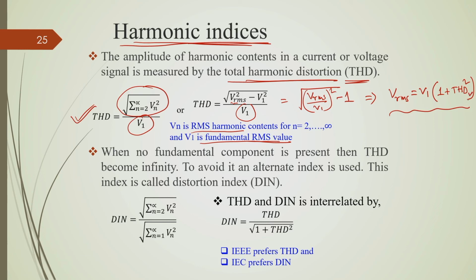So, this is the voltage harmonics which is represented by THD V. Similarly, for current harmonics we can write I RMS is equal to I 1, where I 1 is the fundamental component of the current, multiplied by square root of 1 plus THD I square. So, here this THD I represents the harmonics in the load current or line current. Okay. So, there is another index which is called distortion index. This is for the same purpose, to quantify this distortion. So, that is called distortion index. Here numerator is same as that of THD, and the denominator is different. Instead of this fundamental voltage, it is basically RMS voltage, that is V RMS.